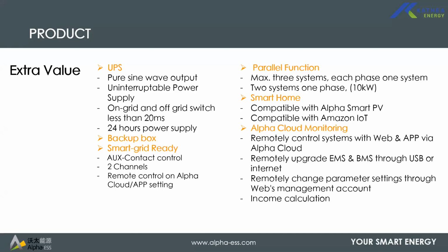So the extra value that the system brings: the inverter is a pure sine wave. So it means it's compatible with our grid regulations, the NRS 97, and it's licensed and certified under the NRS 97-2-1, which is our regulatory grid code. And then the system offers uninterrupted power supply. The system can work as a UPS when you are watching your TV and all that. You won't even notice that the grid is now on load shedding. It offers a 20 millisecond changeover.